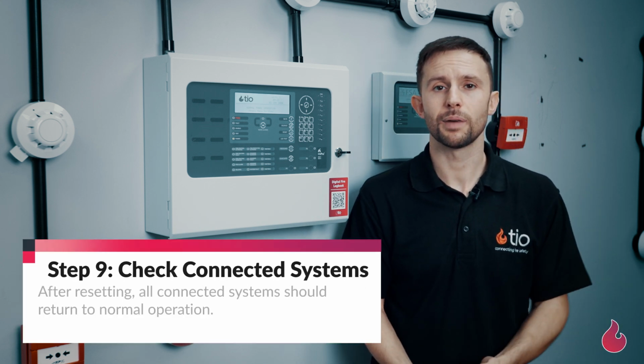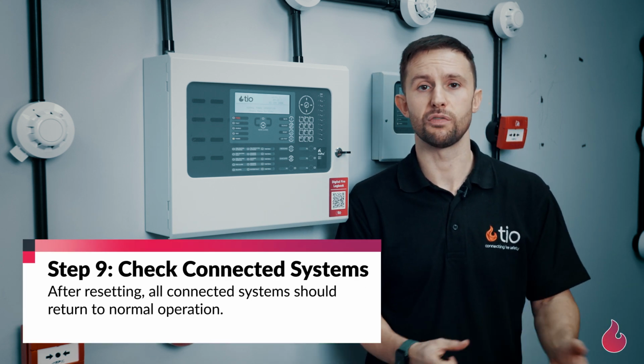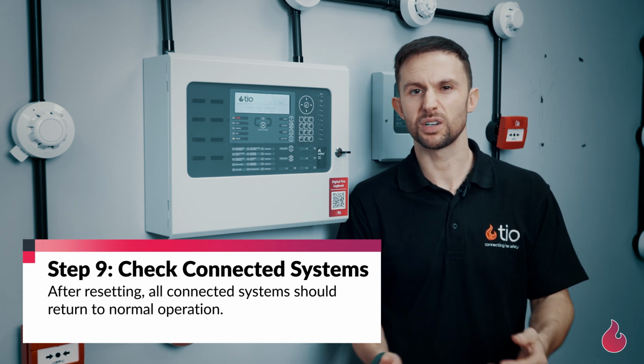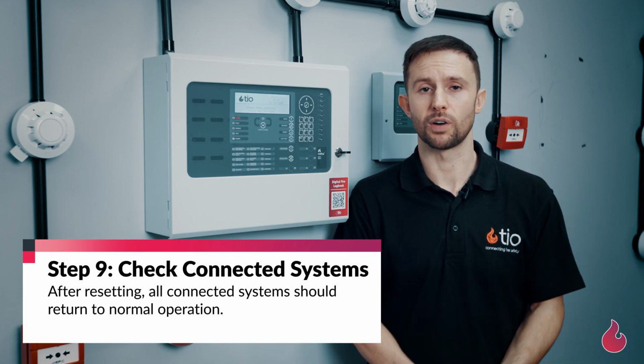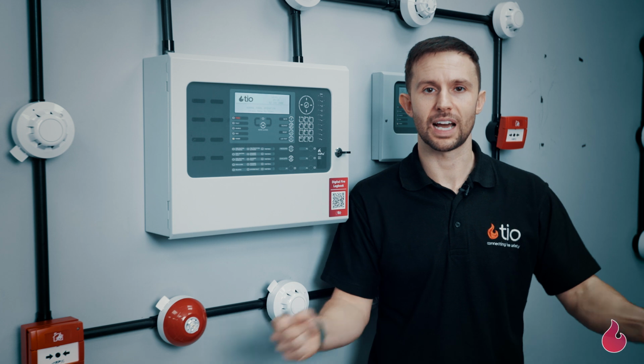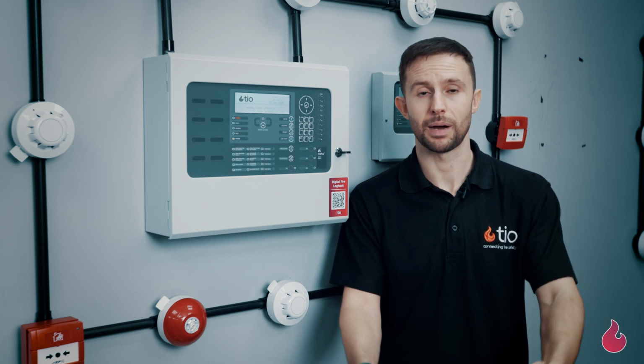Once we've successfully reset the fire alarm system, we'll need to make sure that all the connected systems that switched off earlier are now switched back on. For example, have the lifts come back into operation? Are the doors able to latch onto the magnets? Has the gas come back on, for example?